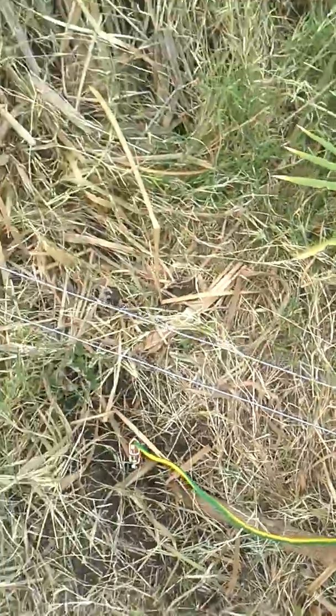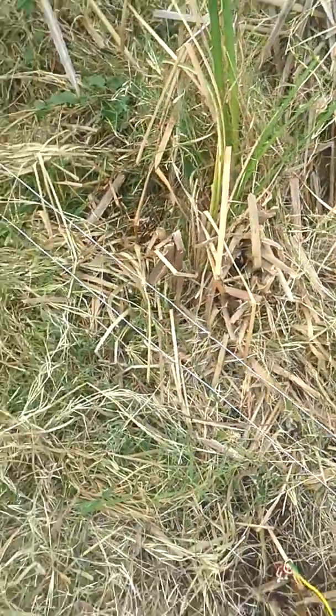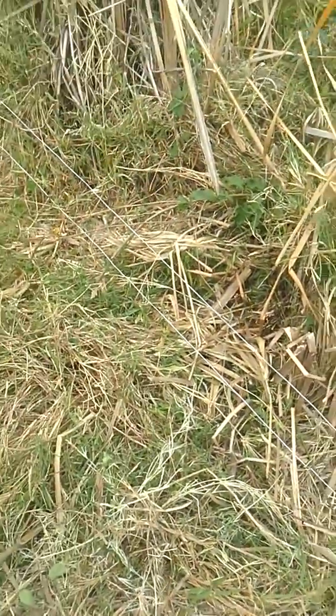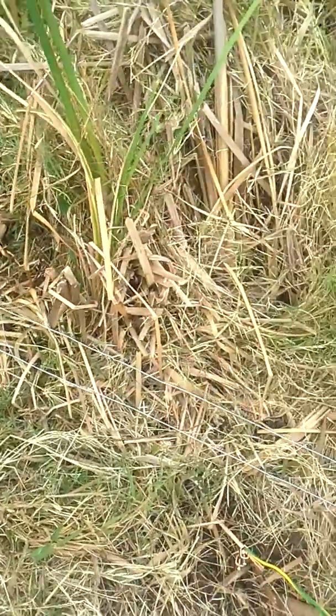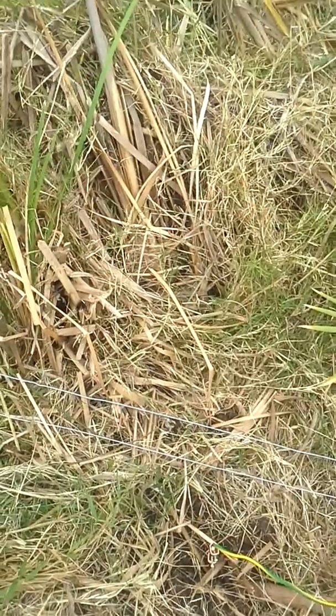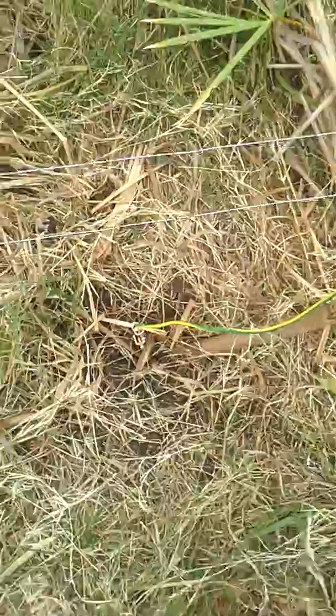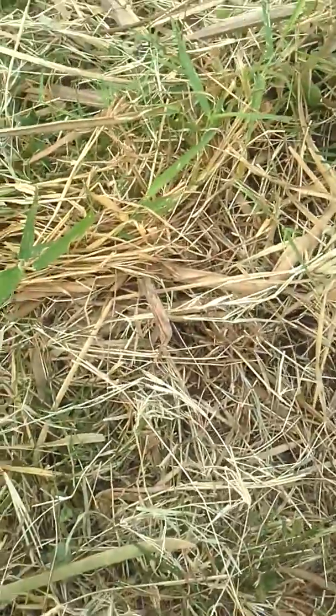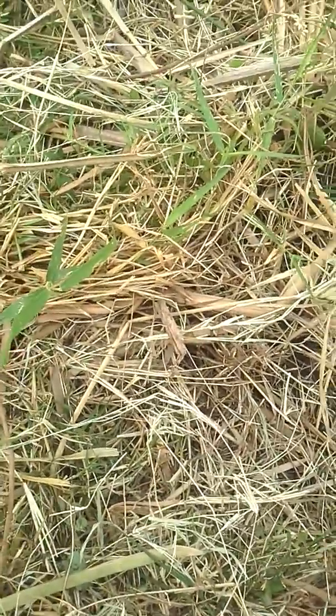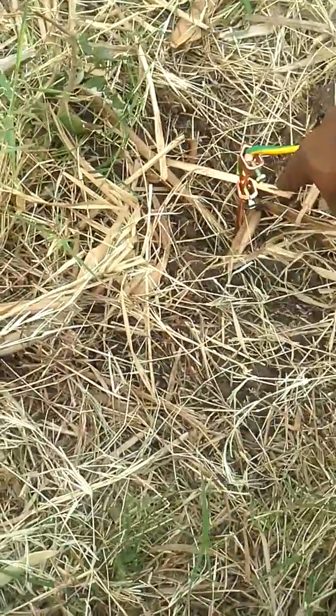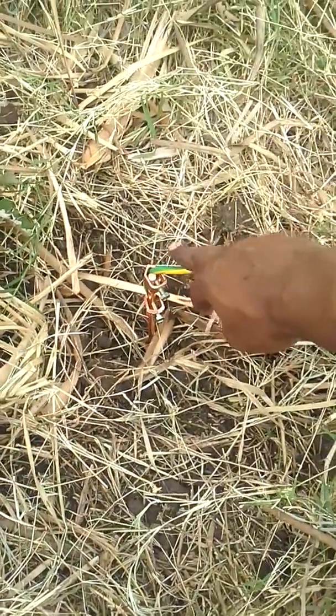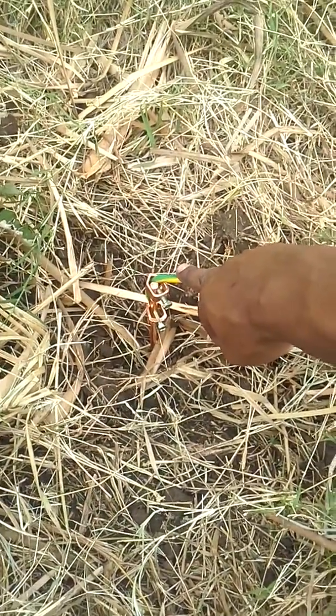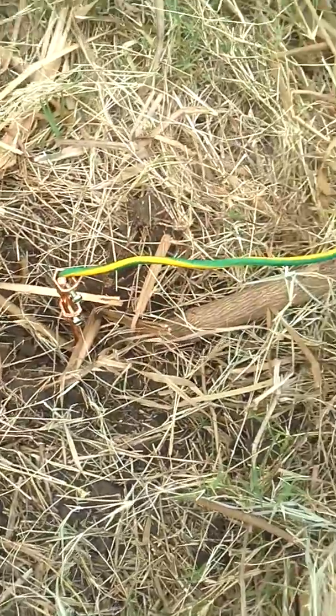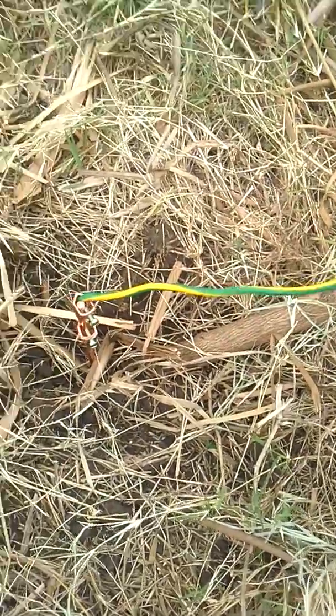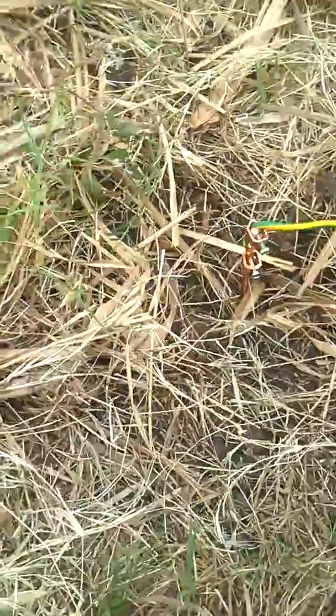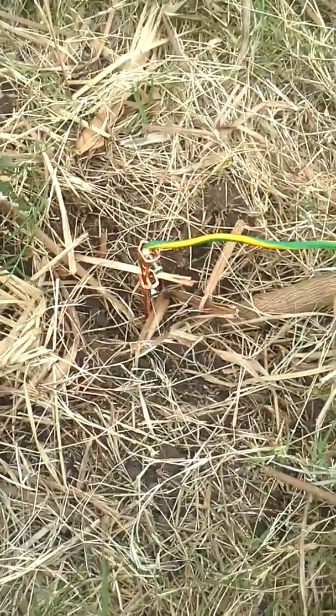Right now that's 20,000 volts, my friends. Whether it's bad or not, there's high voltage, so you have to earth this properly into the ground, or else it's going to be a problem. This has to be properly earthed, because that's what brings the voltage all the way down. I used a thin cable to bring the voltage down, but this is a mistake - this wire is supposed to be thicker.